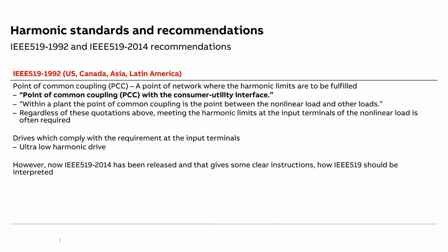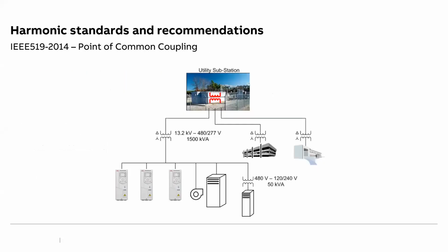Now, as I said, IEEE 519 governs the harmonics, and it calls for various levels depending on the ISC by IL ratio. The most stringent requirement is for 5%, so we have to ensure that. It then talks about harmonics at the PCC. PCC is the point of common coupling. So here we'll see what exactly the PCC is.